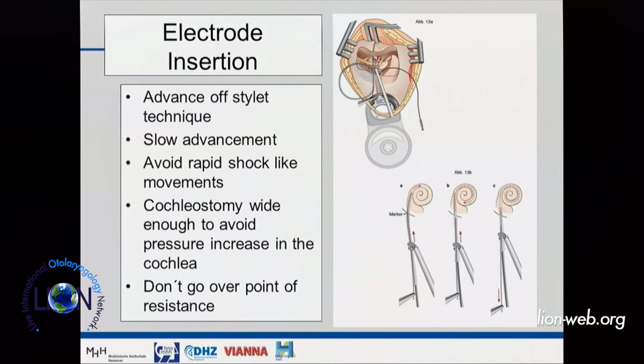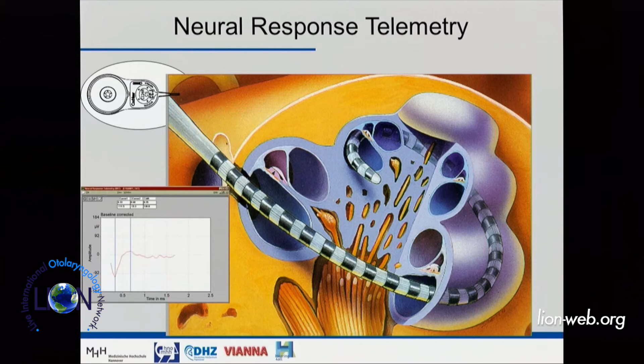So once the electrode is in, we want to make sure that everything works, and then you just stimulate the nerve, and then you can record responses from the nerve. You see here, for instance, this electrode stimulates, then the adjacent nerve will respond, action potential is produced, and then you can record with the device itself with other adjacent electrodes, and this signal then is displayed and can be seen on the screen of the measurement system, and you know the nerve is responding, and for children you also get some values for postoperative fitting.